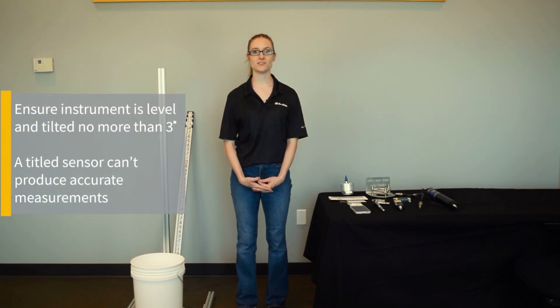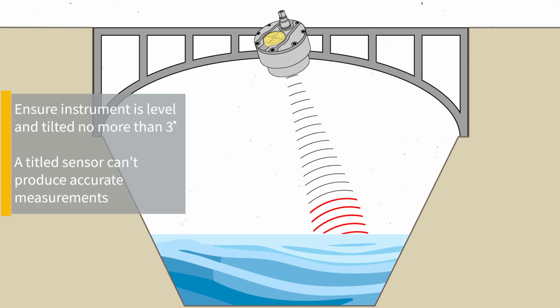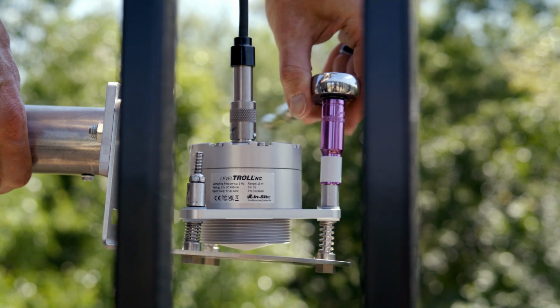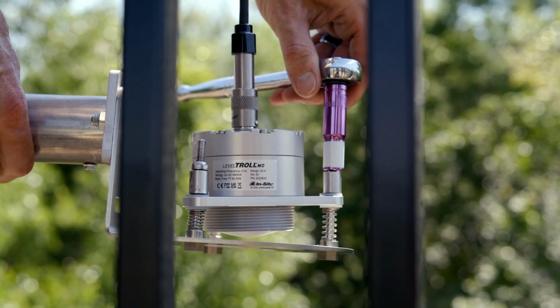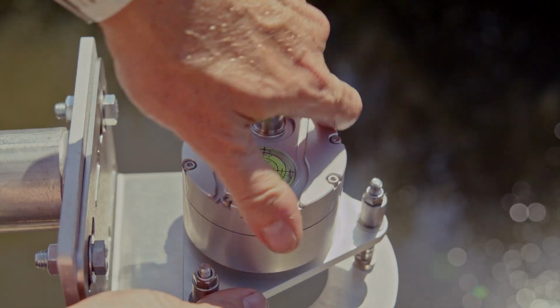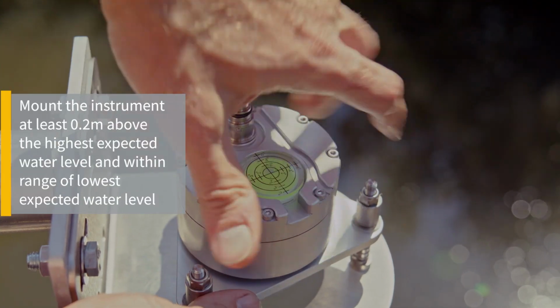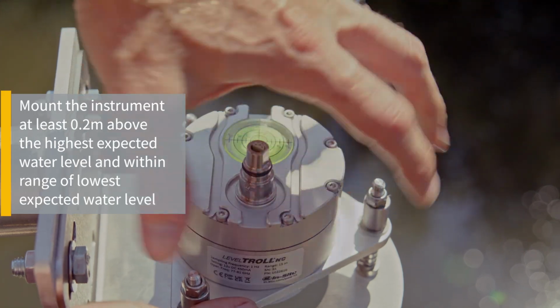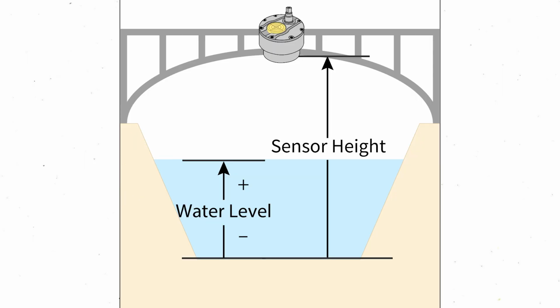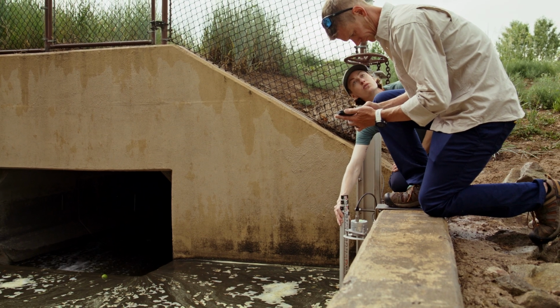You'll want to make sure that the instrument is level, tilted no more than 3 degrees in any direction. A tilted sensor cannot produce accurate measurements. It's easy to check and adjust the sensor tilt. We'll go over how later in this video. Mount the instrument at least 0.2 meters from the highest expected water level and within the instrument's range of the lowest expected water level. Readings may not be accurate if the instrument is too close or too far from the water.